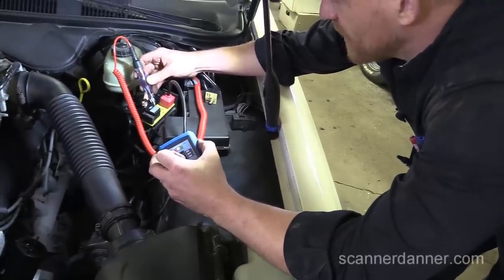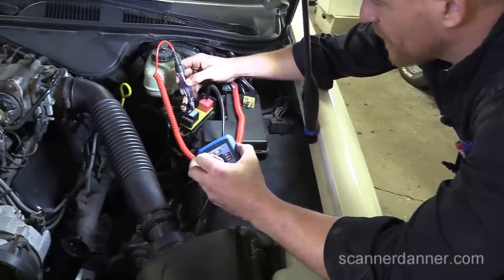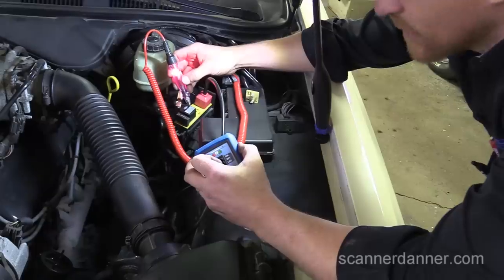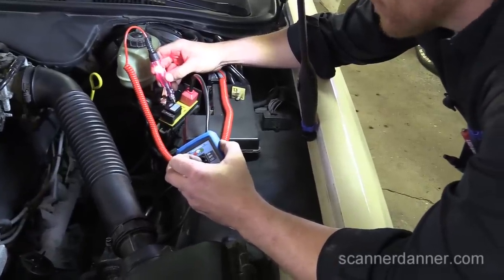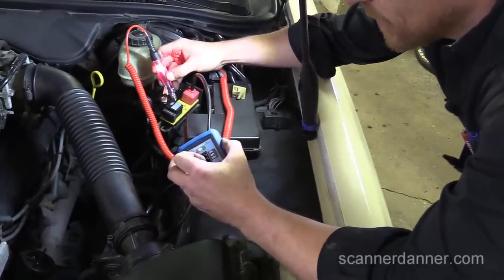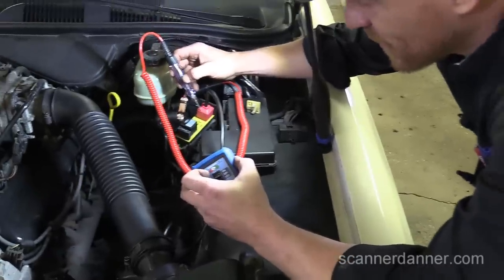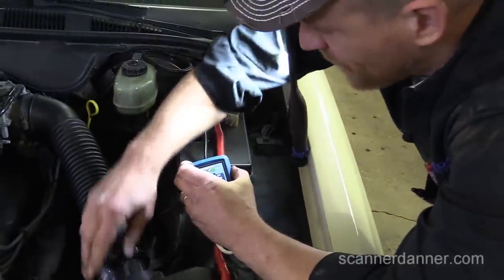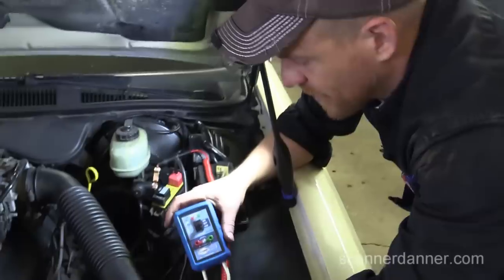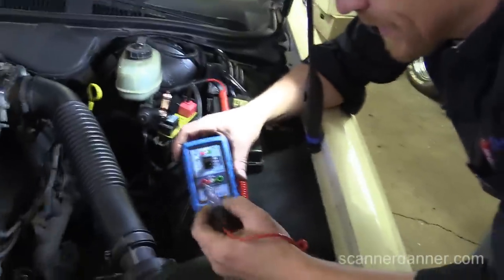The load side of this relay feeds power to the control side of this one, but we still don't have a pump that's operating. And I don't have a power relay that's turning on. I'm missing a power feed on the control side of the power relay.